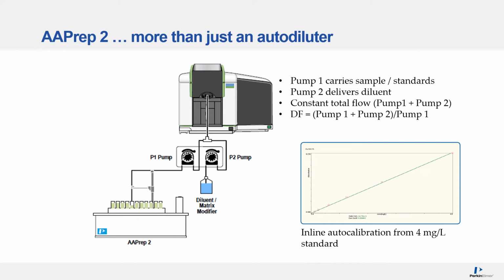And the more-than-an-auto-diluter portion is that it can also do inline auto-calibration from a single stock solution. So in the bottom right-hand corner, there's an example of looking at a single solution where we have started with a 4 milligram per liter standard, and we have diluted that multiple times to create a calibration curve.